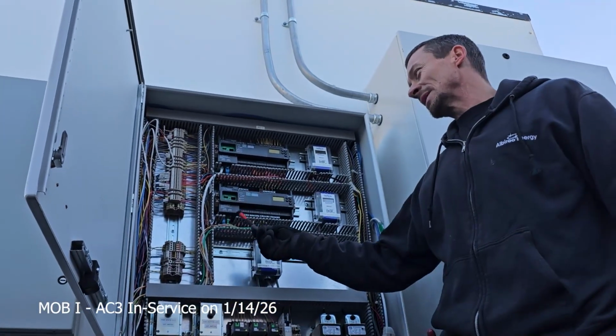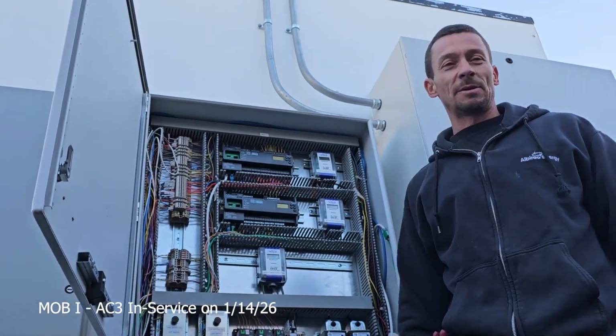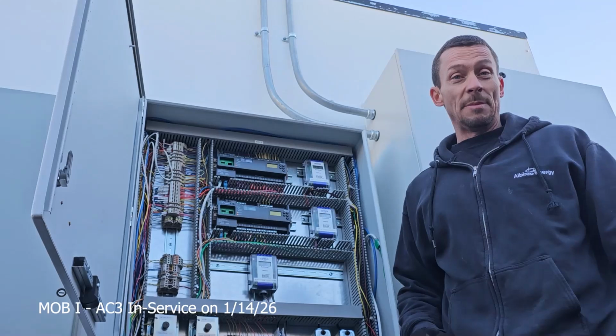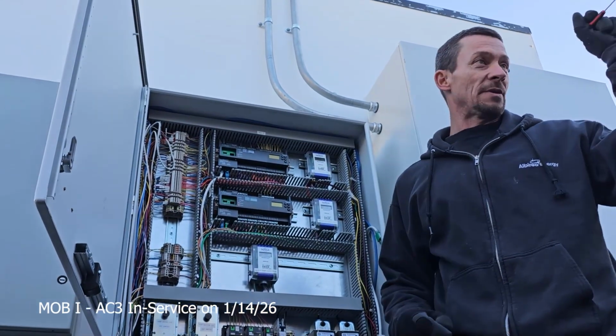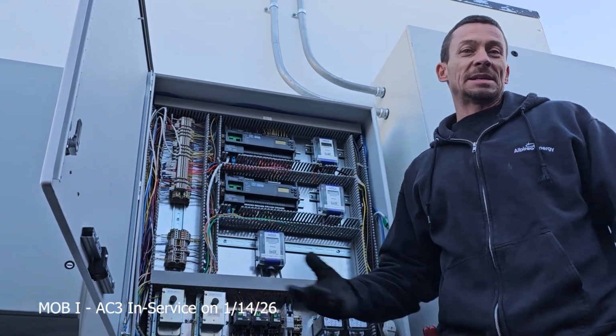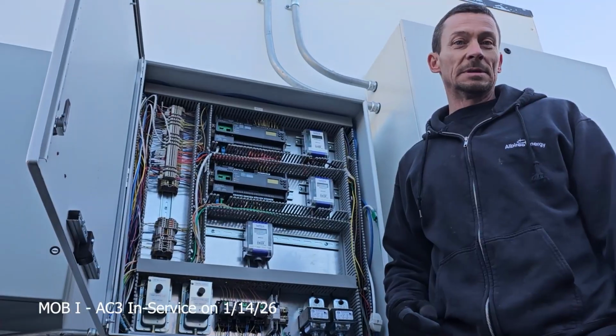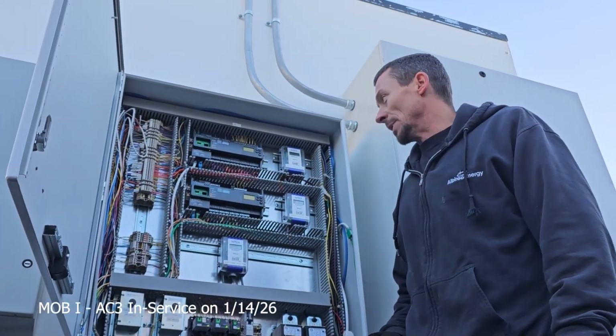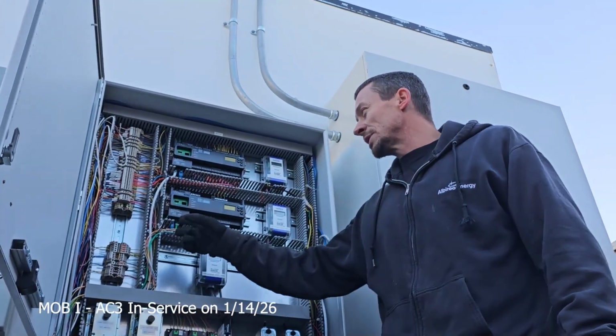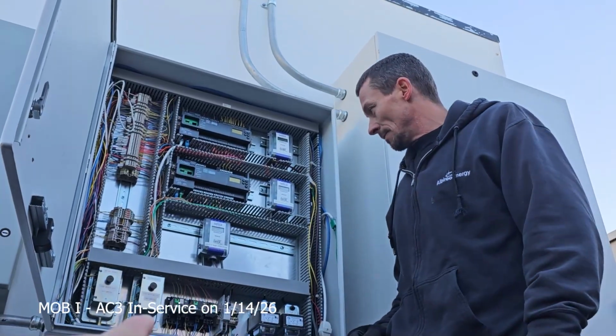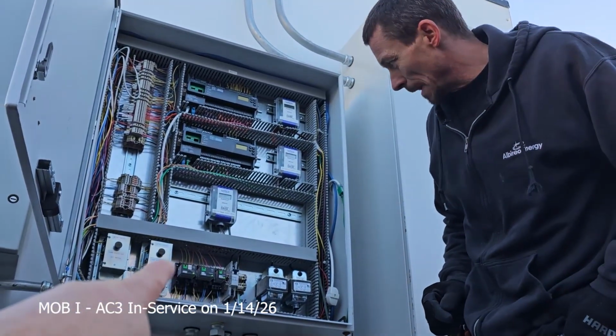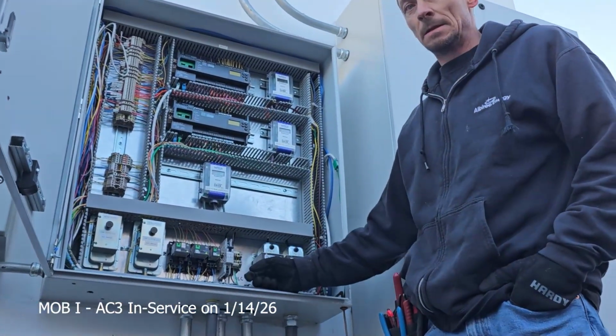You could, typically with Ethernet, I mean, cycling power is probably not going to do it, but you never know. You try. You'd have to shut the power off at that main disconnect right there. That would be the same thing, right? Can we communicate with the MSTP? What is that breaker right there? This is Wi-Fi for the panel. Huh? This is for our panel.